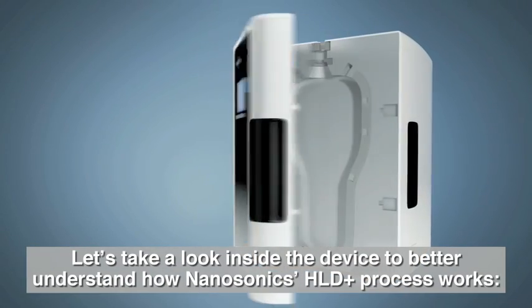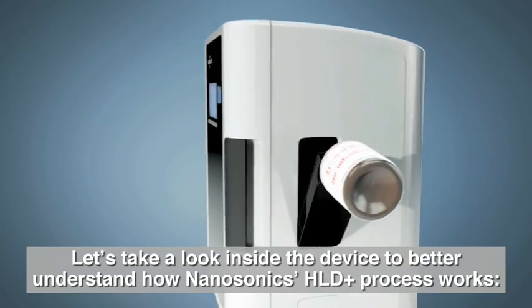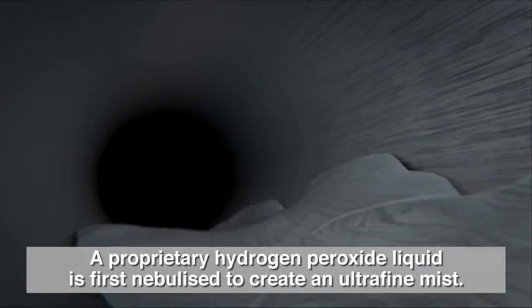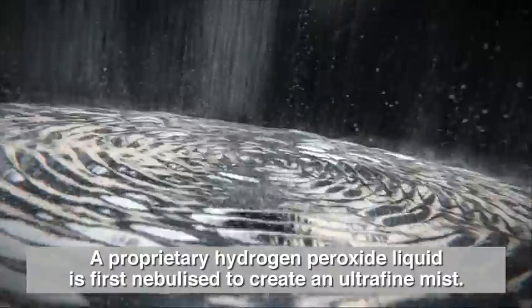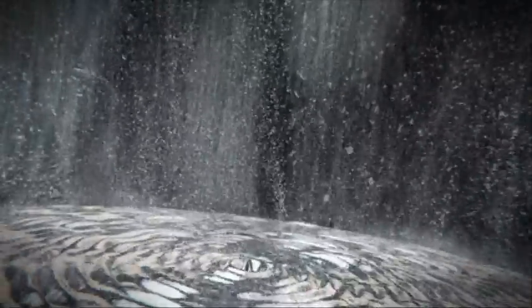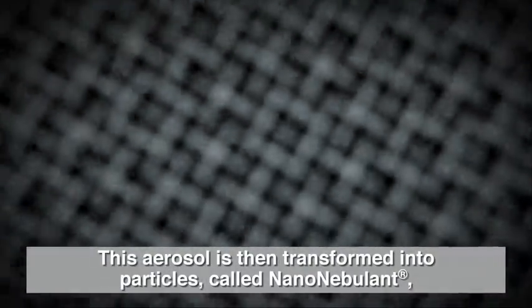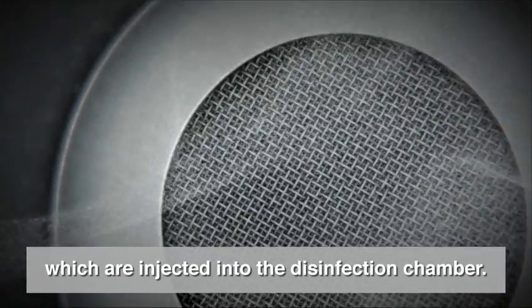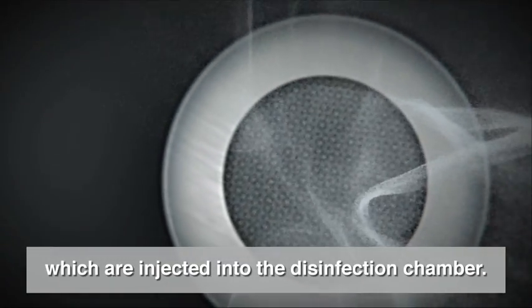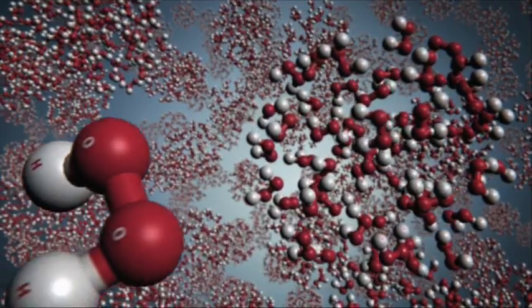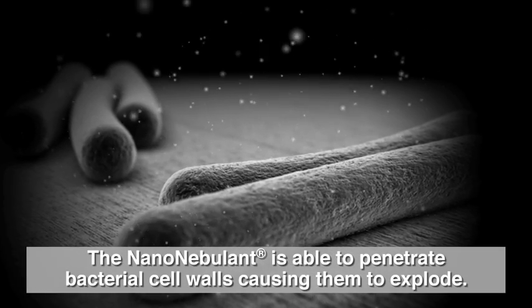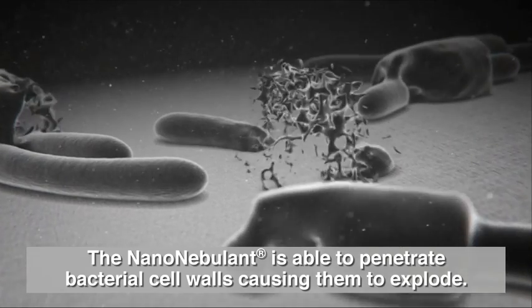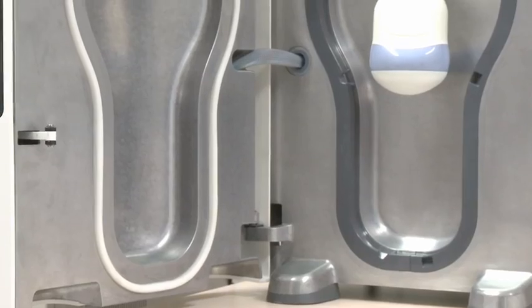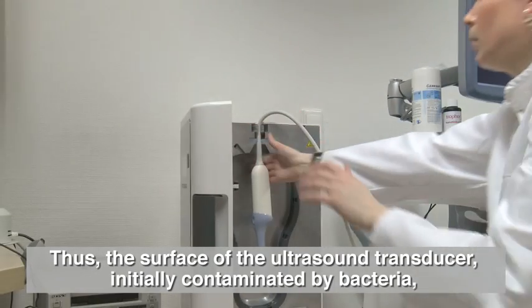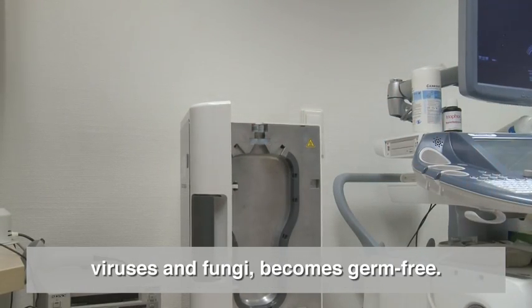Let's take a look inside the device to better understand how Nanosonics' HLD Plus process works. A proprietary hydrogen peroxide liquid is first nebulized to create an ultrafine mist. This aerosol is then transformed in particles called nanonebulant, which are injected into the disinfection chamber. The nanonebulant is able to penetrate bacterial cell walls, causing them to explode. Thus, the surface of the ultrasound transducer, initially contaminated by bacteria, viruses and fungi, becomes germ-free.